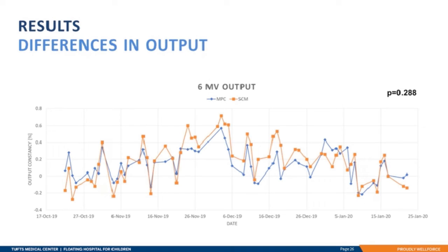While looking at the efficiency of the platforms is important, the collected results and how they compare to each other may be even more important. A fast test is worthless if it is giving inaccurate or inconsistent results. We picked one photon and one electron beam to compare output constancy, as well as our one flattening filter-free beam. Here you can see the results from our 6MV beam.